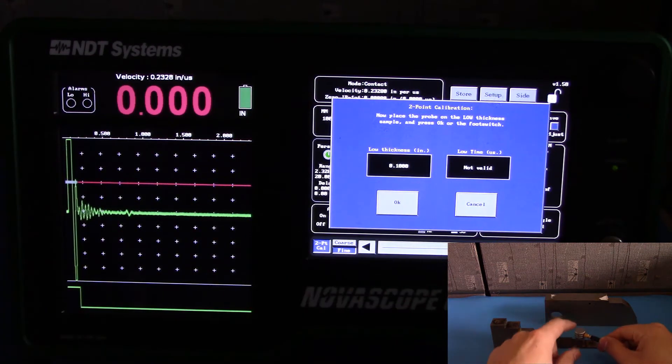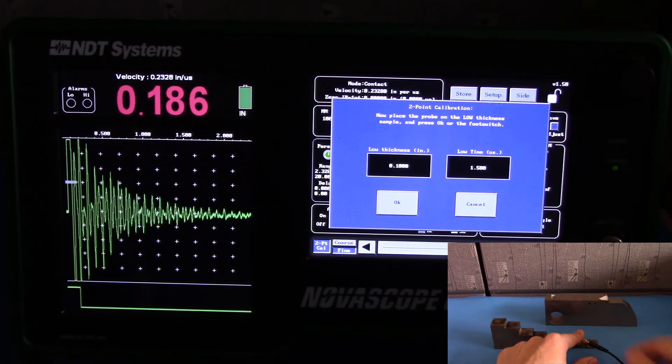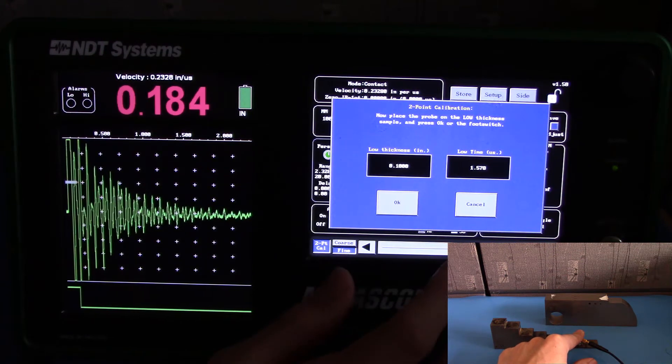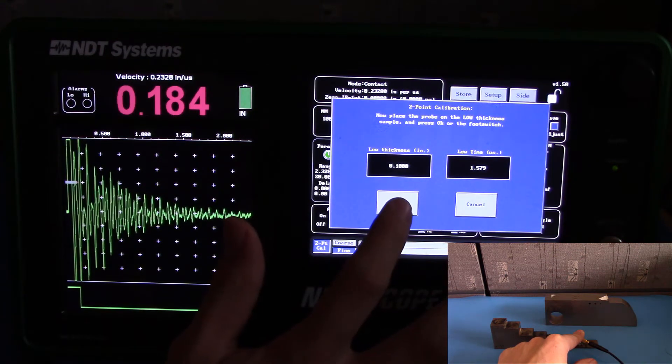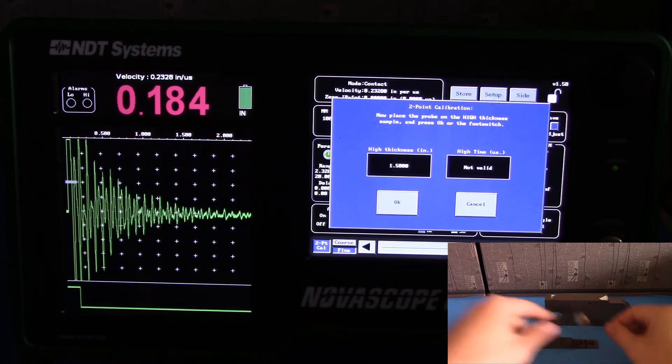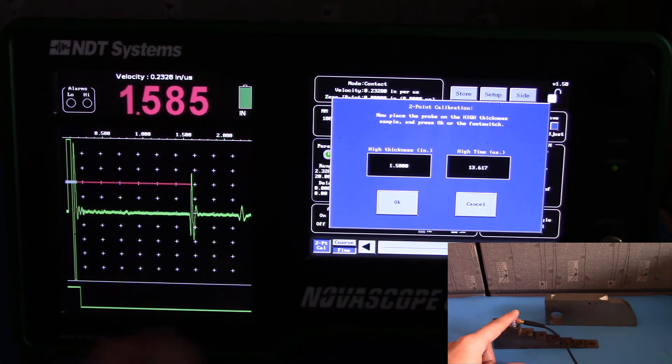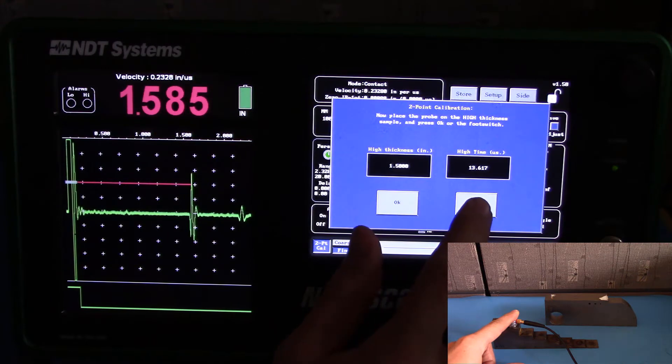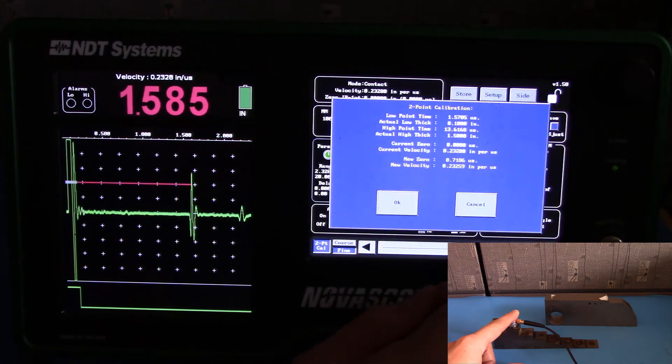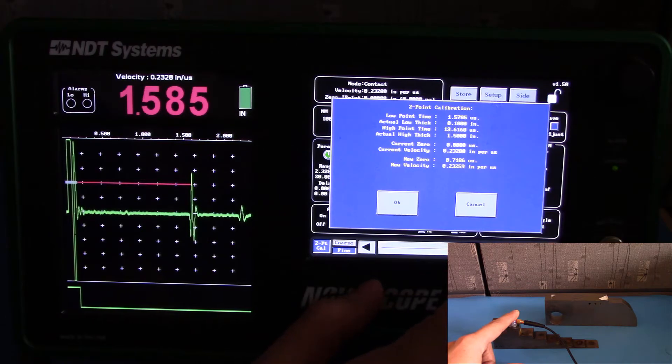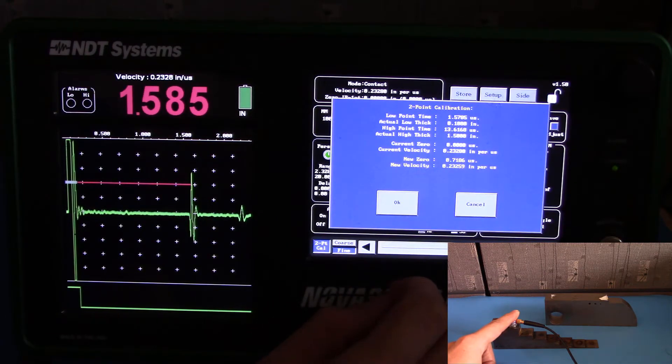Now go ahead and couple to your region of low thickness. When you get a steady reading, hit OK. And go to your region of high thickness. Hit OK when you get a steady reading. And the gauge has now calculated our new zero and new velocity. Hit OK to apply.